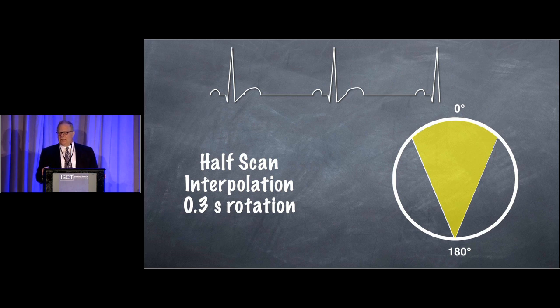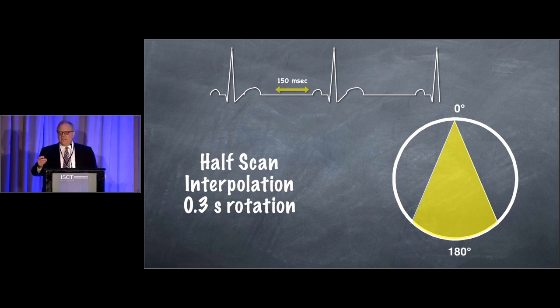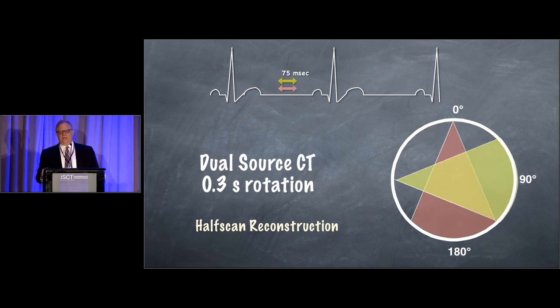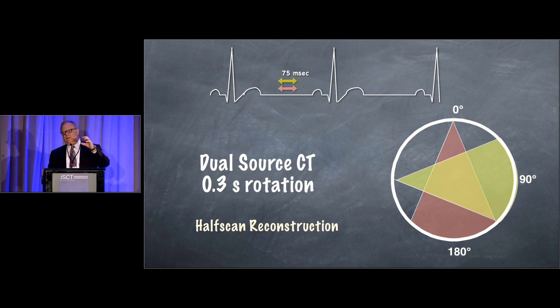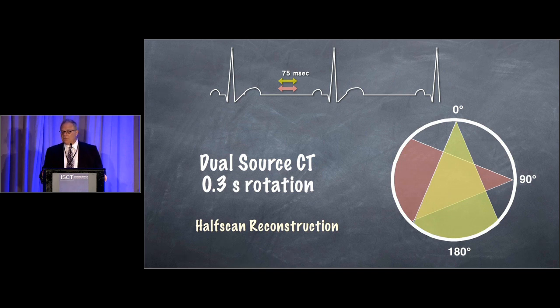The way to think about temporal resolution is that it takes 180 degrees of information to reconstruct a transverse section. With a scanner that rotates in approximately 300 milliseconds — we have 270–280 millisecond scanners — that gives us 150 milliseconds of temporal resolution for a single transverse section. Dual-source scanners have the benefit of only needing to rotate 90 degrees. So if a scanner completes a full 360-degree rotation every 300 milliseconds, one-quarter of a turn takes only 75 milliseconds. A 75 millisecond versus 150 millisecond temporal resolution is a substantial difference for freezing motion.